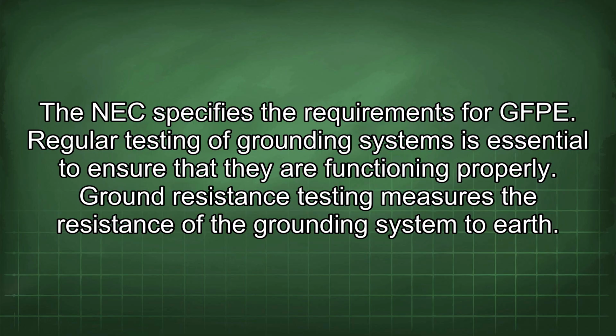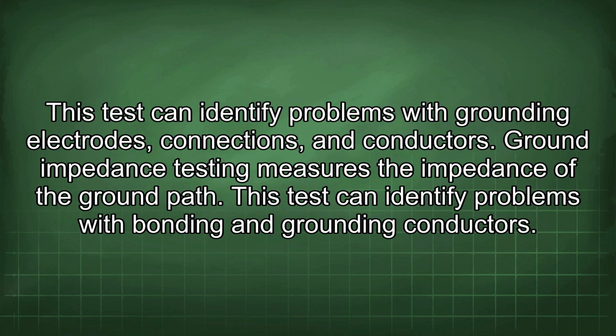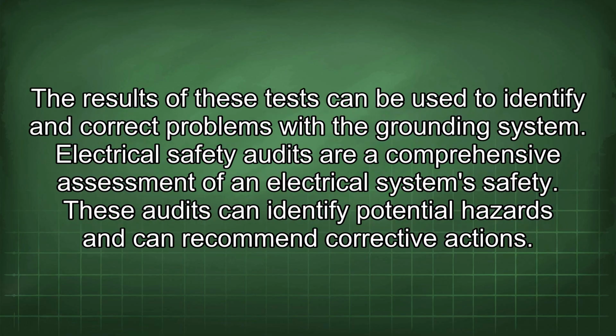Regular testing of grounding systems is essential to ensure that they are functioning properly. Ground resistance testing measures the resistance of the grounding system to earth. This test can identify problems with grounding electrodes, connections, and conductors. Ground impedance testing measures the impedance of the ground path. This test can identify problems with bonding and grounding conductors. The results of these tests can be used to identify and correct problems with the grounding system.